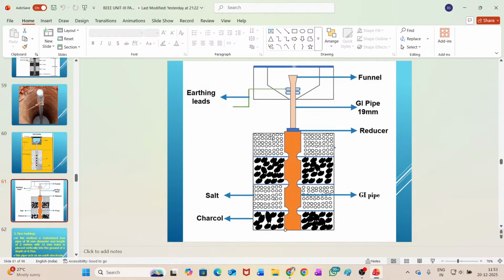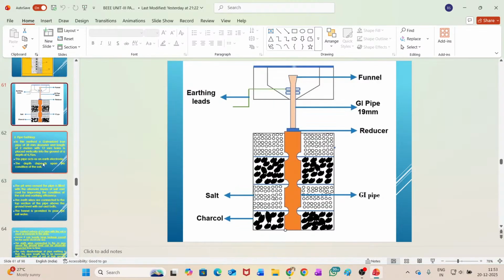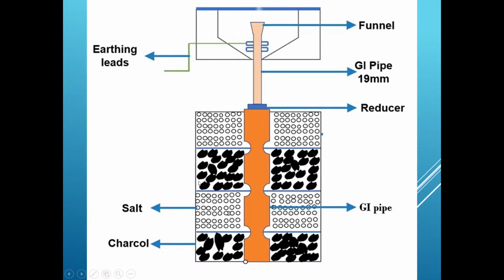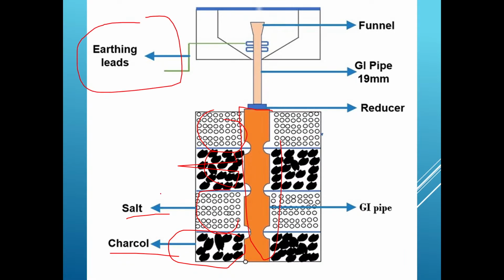I forgot about this — the layers of salt and charcoal provided around the pipe. This is our GI pipe, and these are the layers of charcoal: at the bottom layer charcoal, then salt, next charcoal, next salt. Similar to plate earthing, layers of salt and charcoal are provided around this pipe. The earth leads are brought out above the ground level, which is the advantage of pipe earthing compared to plate earthing.